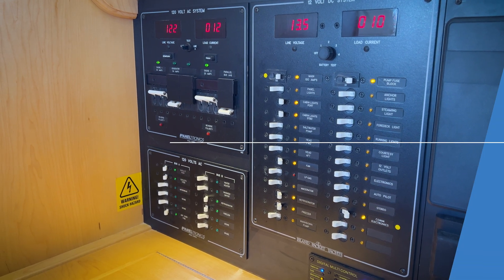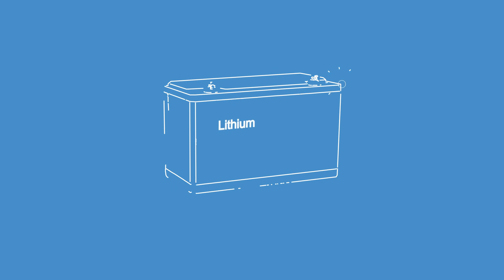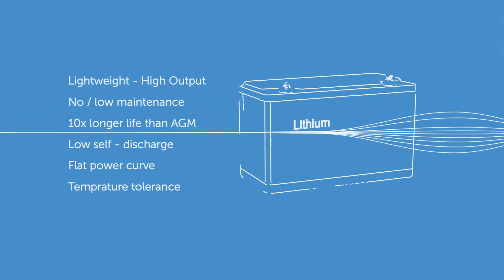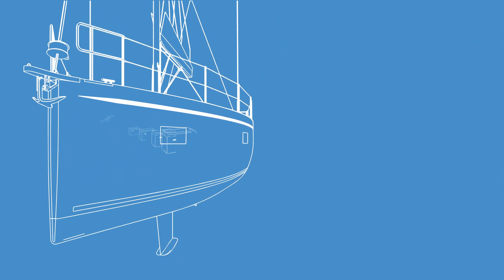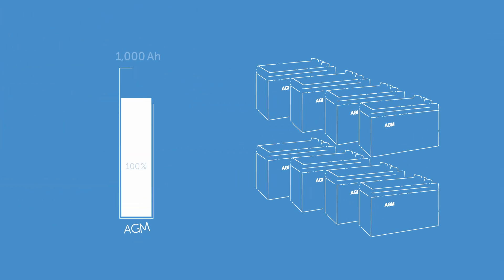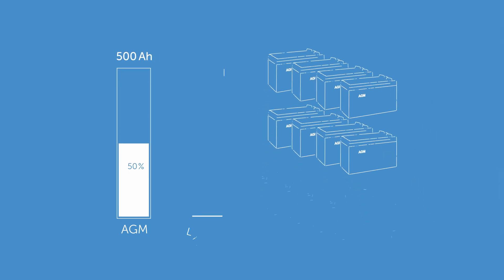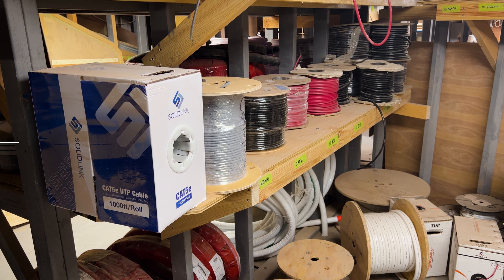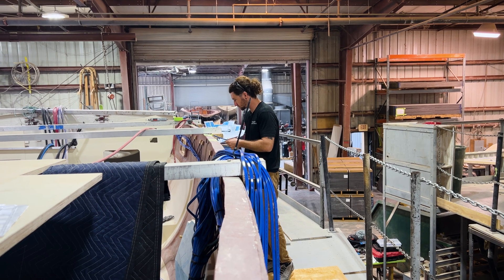There are several benefits to lithium batteries: mainly they're lightweight with higher output in the same space compared with lead acid batteries, they have easy maintenance, and a lifespan up to 10 times longer than AGM batteries. With eight AGM batteries you get 1,000 rated amp hours, meaning about 500 real usable amp hours. With lithium batteries in less space, you can get 1,320 amp hours rated, of which you can use about 1,200.